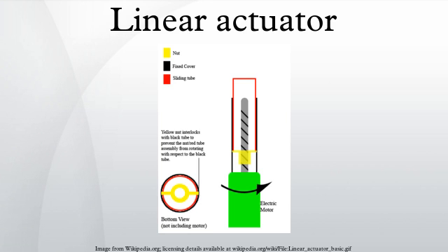Linear motors. A linear motor is functionally the same as a rotary electric motor with the rotor and stator circular magnetic field components laid out in a straight line. Where a rotary motor would spin around and reuse the same magnetic pole faces again, the magnetic field structures of a linear motor are physically repeated across the length of the actuator. Since the motor moves in a linear fashion, no lead screw is needed to convert rotary motion to linear.